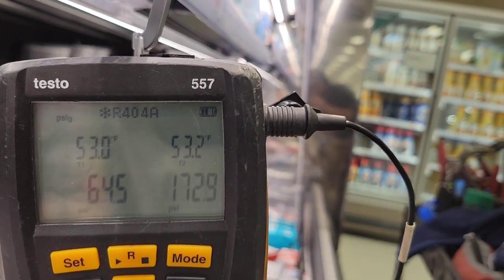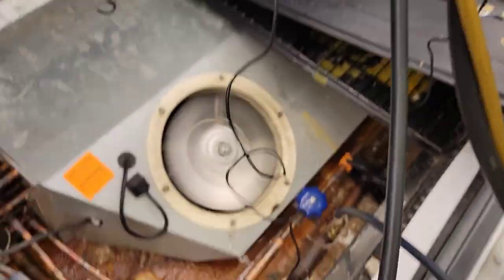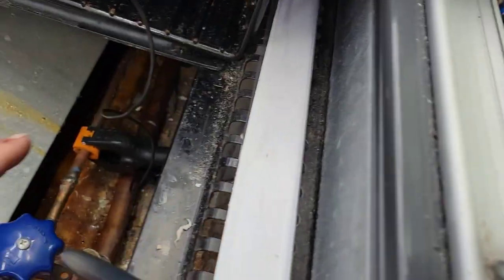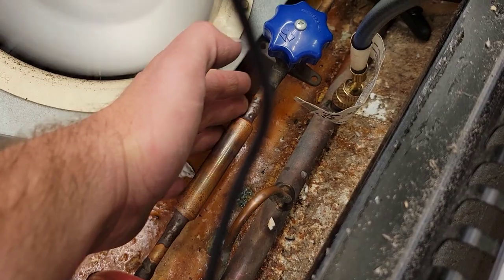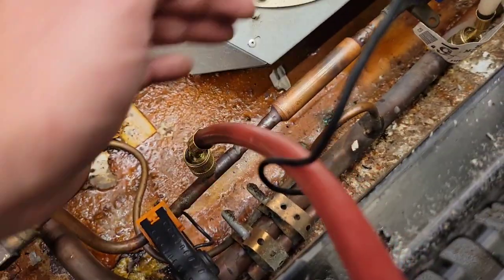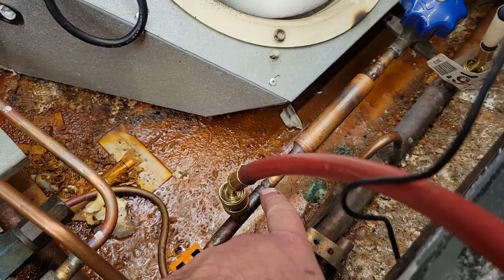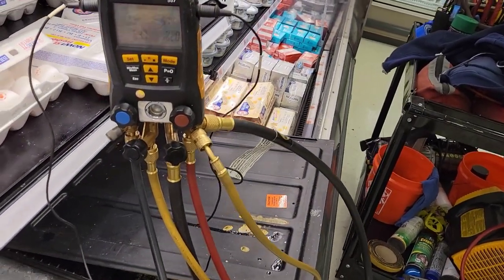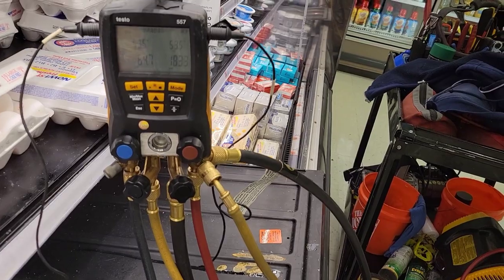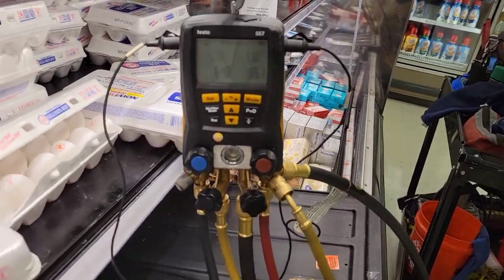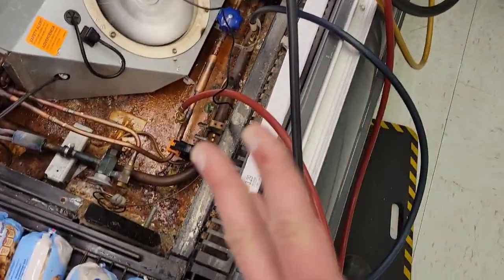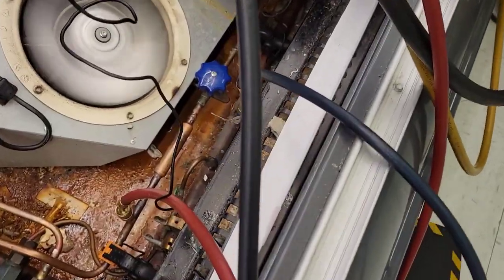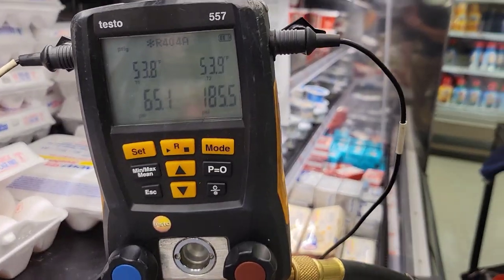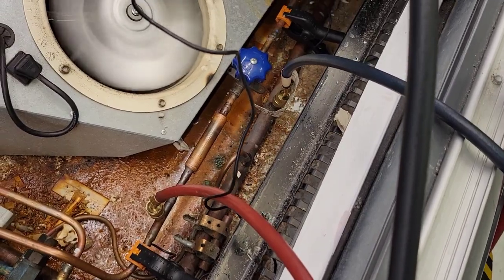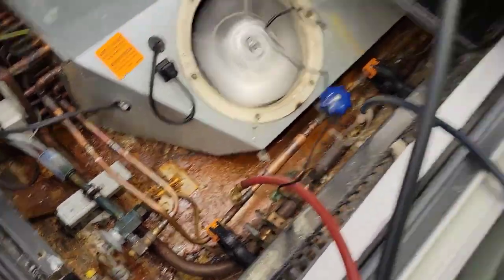So as you can see, temperature 1 is 53, temperature 2 is 53. They've been sitting there about 5 minutes. Temperature 1 is here, temperature 2 is over there, on two different sides of this screen. So if the screen was clogged, the refrigerant's coming in this way, and on this side it would be a much lower temperature. For me, typically, if I see anywhere above 3 to 4 degrees difference, I start to take concern with it. So that's a rule of thumb. It just depends on your case and how volatile the system is. But you would do the same thing if it was a filter dryer. This case just happens to be a screen. So now I'm going to take the superheat and see what that gives me.